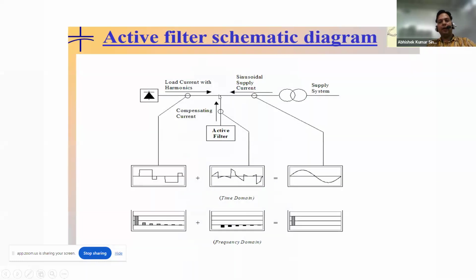So now, how does an active filter improve the system efficacy? Suppose this is a load current with harmonics. This is the sinusoidal supply current, and this is the active filter. So these are the harmonics which are produced in the system. These are the harmonic currents. What it will do is inject the same into the system in mirror image and nullify the impact of harmonics. So the final resultant will be this. We will get what we want to achieve. So this is the advantage of having an active filter in the system.